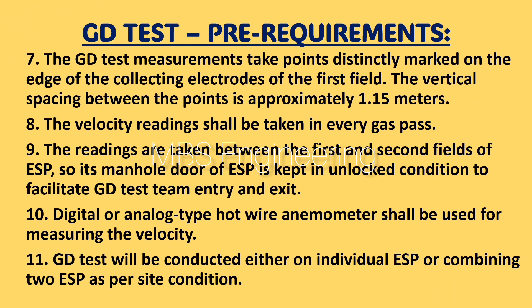Point 7: the GD test measurement points are distinctly marked on the edge of the collecting electrodes of the first field. The vertical spacing between the points is approximately 1.15 meters. Point 8: velocity readings shall be taken in every gas pass.